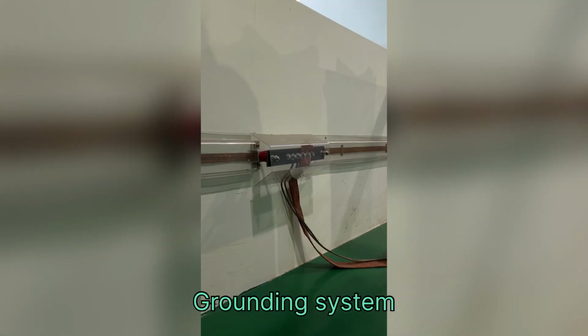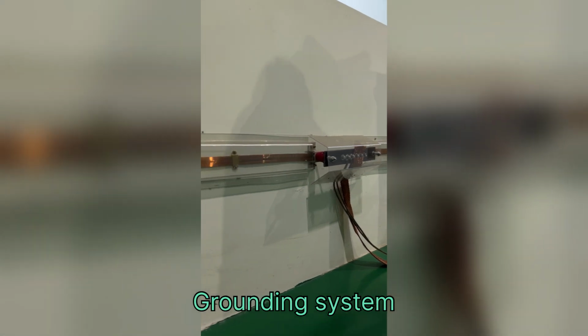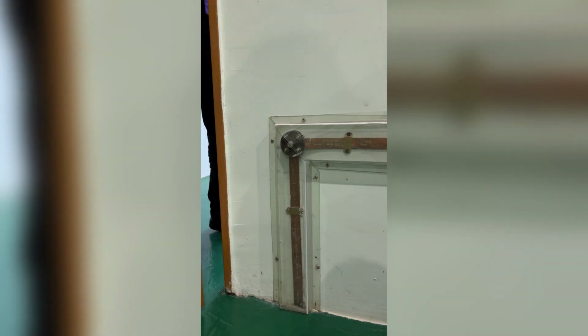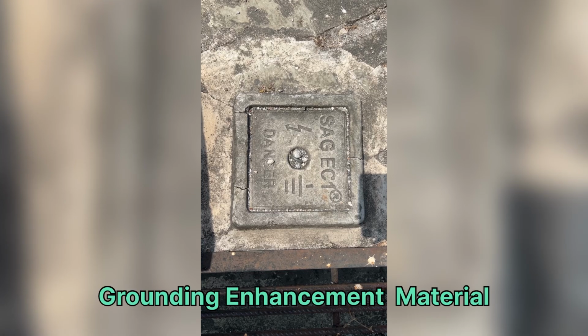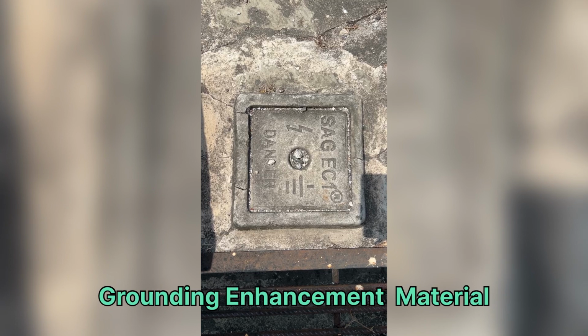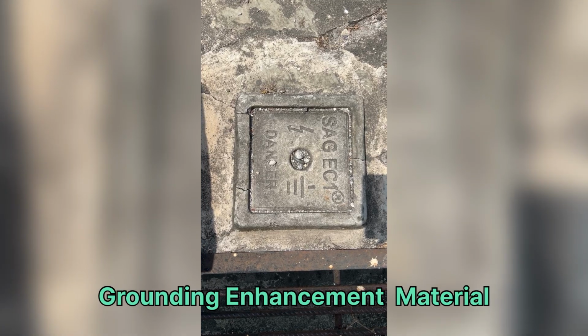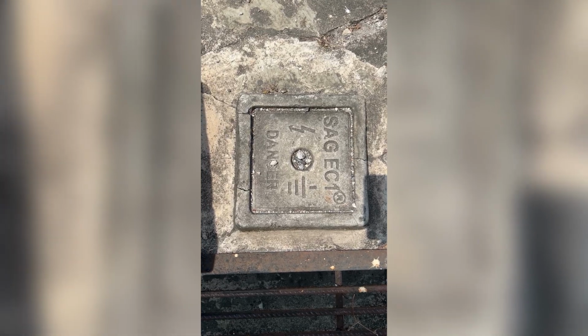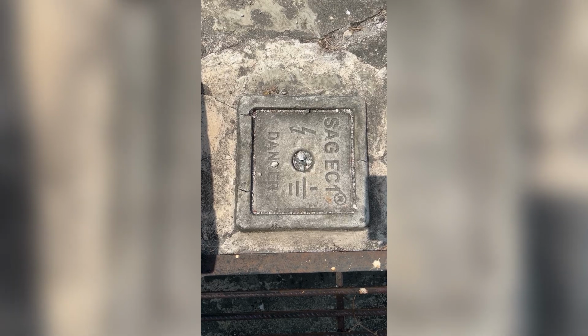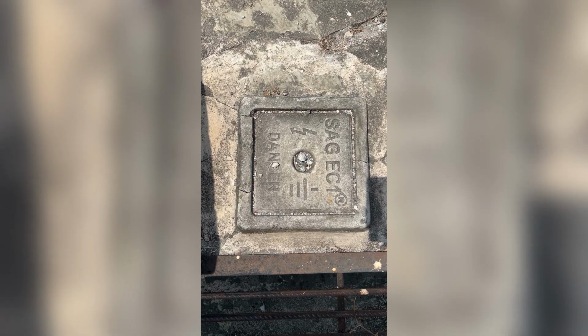The next one is the grounding system. Grounding system circuit must be considered from the main grounding chamber outside of the high voltage lab and is grid at each grounding terminal cell, and from the grounding terminal cell to the frequency converter. These switches can be used as a ground switch or something else. They can be switched in any state of the software: power off, HV ready and HV on.